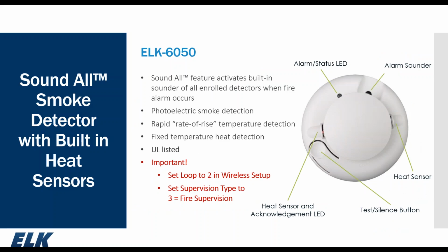The 6050, this is our sound-all smoke detector. It has an 85 decibel sounder built into it. When this detector goes into alarm, it sends a signal to the M1. The M1 will then send the signal back to turn on the sounder. It will also turn on the sounder for any other 6050s which are programmed into the system. Likewise, if the M1 should go into alarm, either from a hardwired smoke detector, 2-wire or 4-wire, or a panic key on a keypad is pressed, it will then send that same signal. So now you have all of your 6050s with their 85 decibel sounders going into alarm during a fire alarm condition.